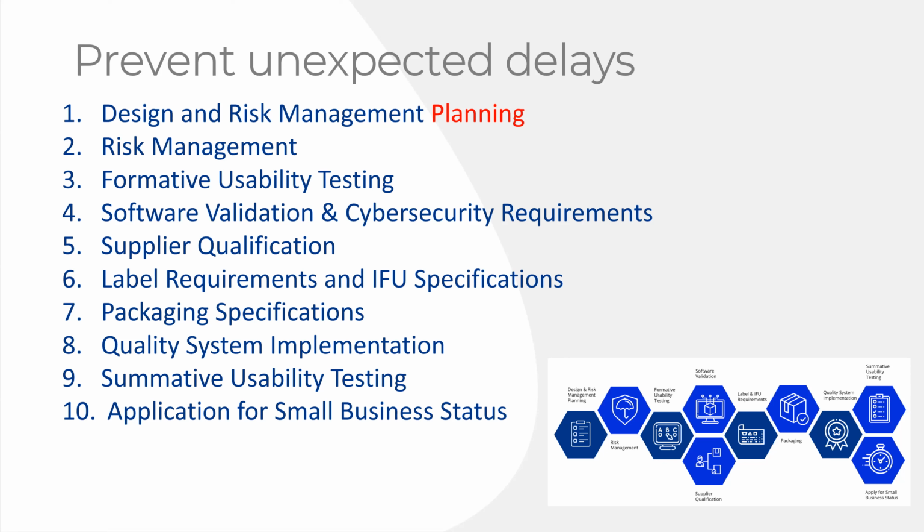For the software validation in cybersecurity, any device that has software requires software validation, and you have to submit 11 documents to the FDA. They also want off-the-shelf software documentation as well, and there's a guidance document for off-the-shelf software. And then they have 2 cybersecurity documents. One's from 2014, I think the other one's 2016, and talks about cybersecurity post-market surveillance.